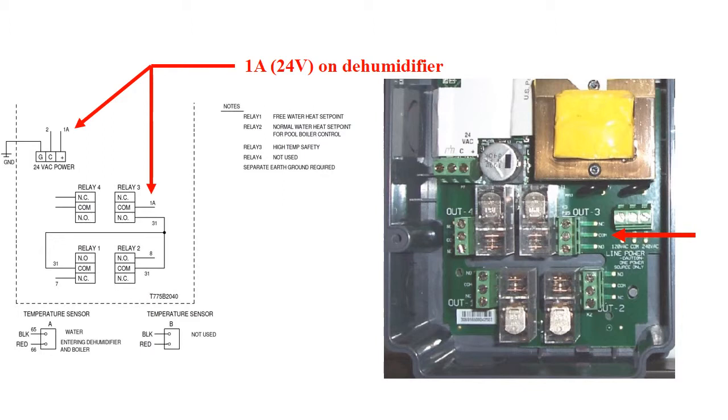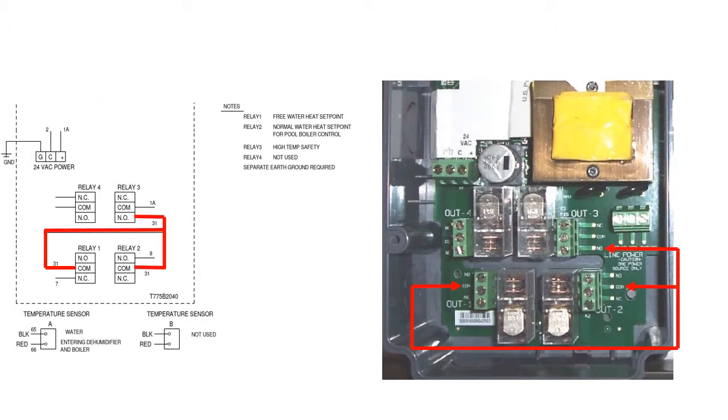The number 1A next to it tells us that it too, like the positive on the power strip, connects to a 1A terminal on the dehumidifier. The normally open terminal on this relay is connected to the COM terminals on relays 1 and 2 by a wire here labeled number 31.